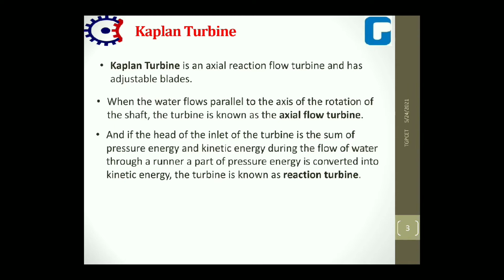A Kaplan type hydraulic turbine is one in which the positions of the runner blades and the wicket gates are adjustable for load change with sustained efficiency. It is a purely axial flow turbine with a vertical shaft, designed and developed by an Austrian engineer, Victor Kaplan. A Kaplan turbine has adjustable runner blades, with a small number of blades, that is 3 to 8. Kaplan turbines are now widely used throughout the world in high flow, low head power production.